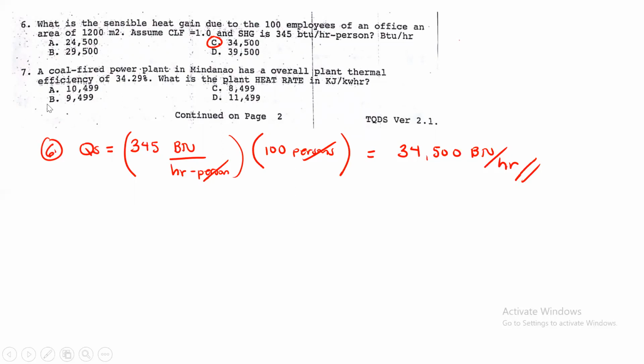So 7. A coal-fired power plant in Mindanao has an overall plant thermal efficiency of 34.29. So dito, hinahanap natin plant heat rate in kilojoules per kilowatt hour. So itong 7. So syempre, para makuha natin yung heat rate, so guys, meron kasi tayong formula, no? Thermal efficiency is equals to 3,600 over heat rate. So itong heat rate na to, naka-kilojoules per kilowatt hour.